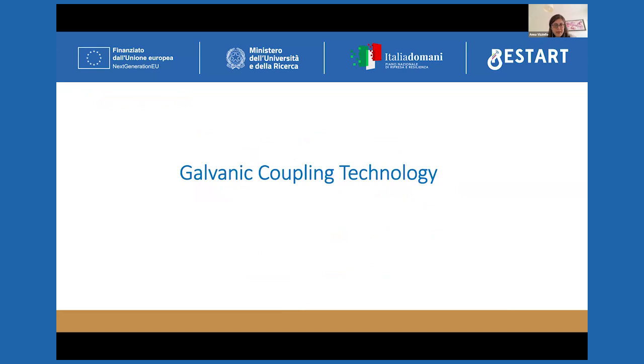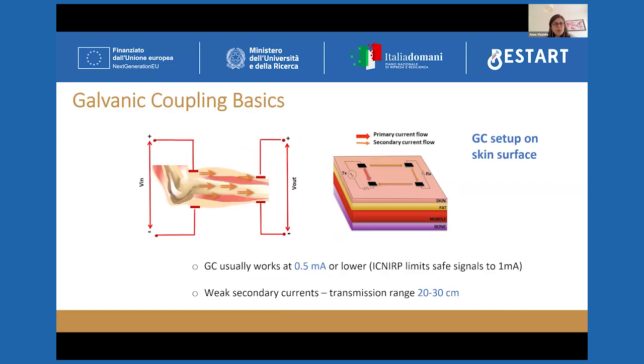Now I'm moving to the galvanic coupling technology, which is the technology I work on. So basically, the working principle is that you have two electrodes in the transmitter and two electrodes in the receiver. As you see on the right, there is one main circuit between the electrodes of the transmitter, and the main primary current flows in this circuit. Anyhow, there are some secondary weak currents, the orange ones, that flow in other tissue. And these currents may be detected by the other two electrodes, represented by the receiver.